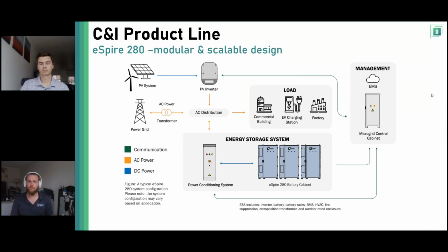This is a rudimentary line diagram, just a representational visual approach to how we AC couple these systems. That's good to note - this is going to be an AC coupled system for the time being. DC coupling is in development, but for now the Espire 280 is AC coupled only. You see the grid power coming in from the left, typically stepping down from grid voltage to 480 volt. We are typically AC coupling to a 600 or 800 amp distribution panel, the same panel typically connected to the PV inverters.